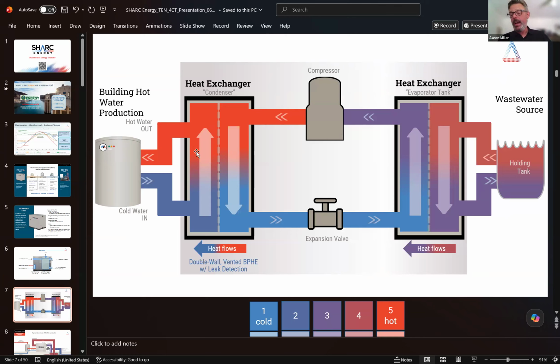What that means is it's designed for potable water, meaning that the refrigerant and the potable water are completely separated by an air gap. There's no cross contamination. So what we do is we run this refrigerant through this way through the compressor and run domestic cold fresh water in opposite flow. And the speed through which we run that cold water through this exchanger determines the set point. We can give you 140-degree Fahrenheit hot water all day, every day, out of the 70-degree water coming out of your building.